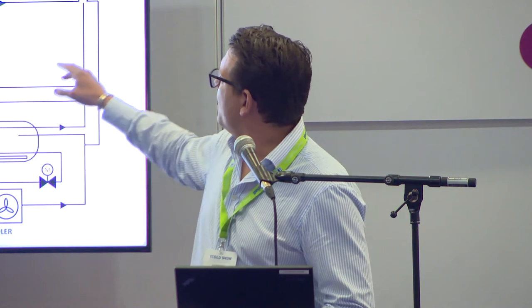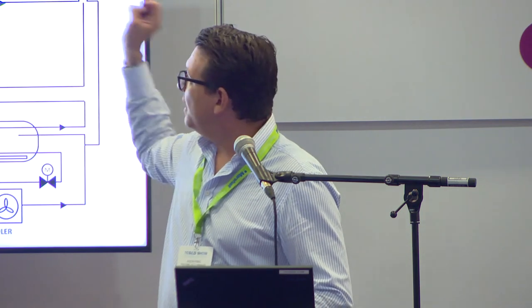The gas, or the suction vapor, then passes down the pipe, through a heat exchanger which pre-subcools your liquid into the LPR, and then back up to your compressor, through your gas cooler, and into the interstage vessel, where it goes from a high pressure gas into a high pressure liquid. So this application was for a 5,300 cubic meter chill store, which is a production facility for processing potatoes.